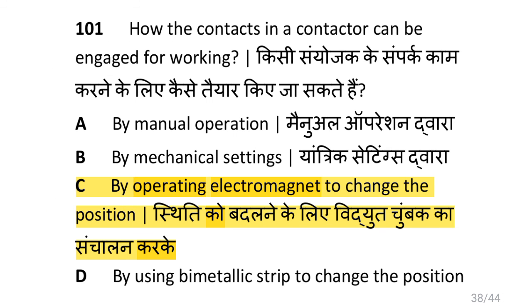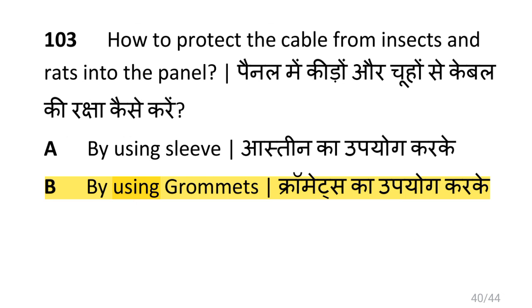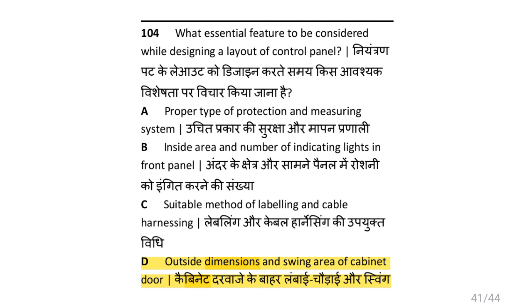How can the contacts in a contactor be engaged or operated? i.e. by operating the electromagnet to change the position. Which device prevents flare out of stripped and stranded cable in the panel board? i.e. lugs and thimbles. How to protect the cable from insects and rats entering the panels? By using grommets. What essential features are to be considered while designing a layout of a control panel? i.e. outside dimension and swing area of the cabinet door.